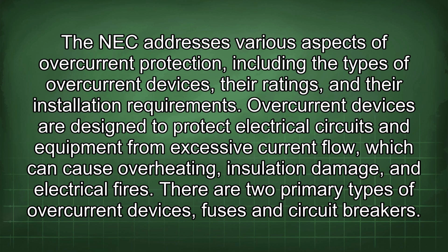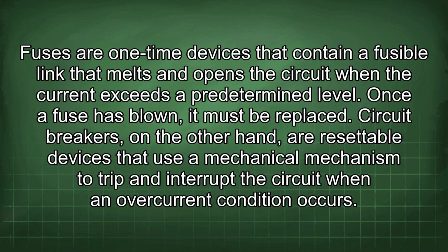Overcurrent devices are designed to protect electrical circuits and equipment from excessive current flow, which can cause overheating, insulation damage, and electrical fires. There are two primary types of overcurrent devices: fuses and circuit breakers. Fuses are one-time devices that contain a fusible link that melts and opens the circuit when the current exceeds a predetermined level. Once a fuse has blown, it must be replaced.